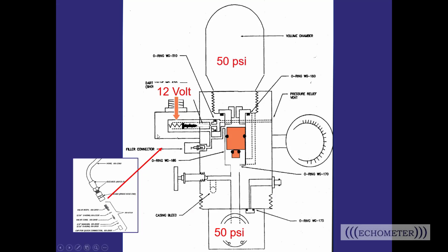So a couple of problems that we see is if you're filling up the gun, and as soon as you pull the hose out of the filler connector, the gas just comes right back out at you, right? So there's a couple of things. And you think about the operation and what happens. So it could be, there's a little valve core in here that maybe needs to be replaced. Possibly the gas valve, you can sometimes hear that gas valve when it goes on the seat, maybe your orifice is clogged. And so the pressure is not able to get up inside the volume chamber. And so it's just blowing right back out at you.